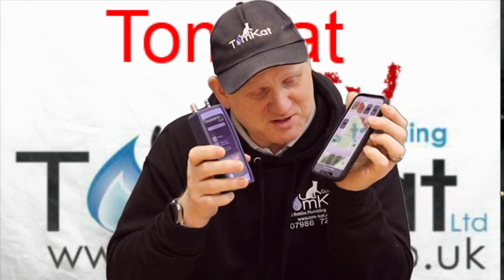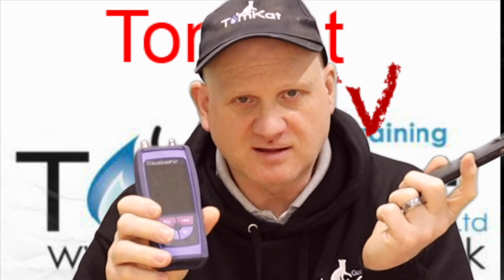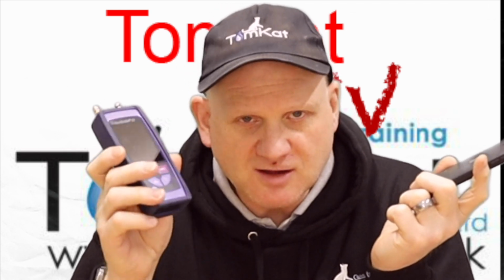So this gives me the best of everything. When it comes to my perfect flue gas analyzer, this little bluelyzer ST is not far off what I want from an analyzer. It does tightness testing. The gas sniffing you use a separate little device, but it all mirrors on my phone as well as on the unit, so that's a good start.